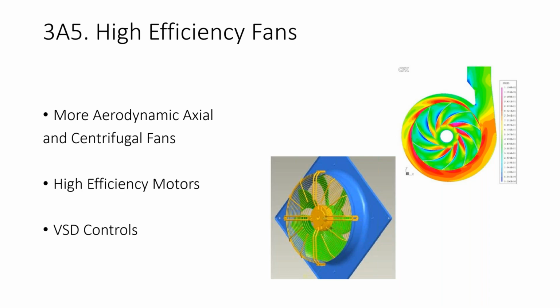Through research and development, we are able to make our fans more aerodynamic. More aerodynamic means that they can push more air with the least resistance. And we have our aerodynamic axial and centrifugal fans, which are the most used fans in AC systems. Those fans use high efficiency motors, which further decrease their energy use, and they are all controlled by variable speed drives. So you can cut it to a third in terms of energy consumption compared to an old kind of fan.